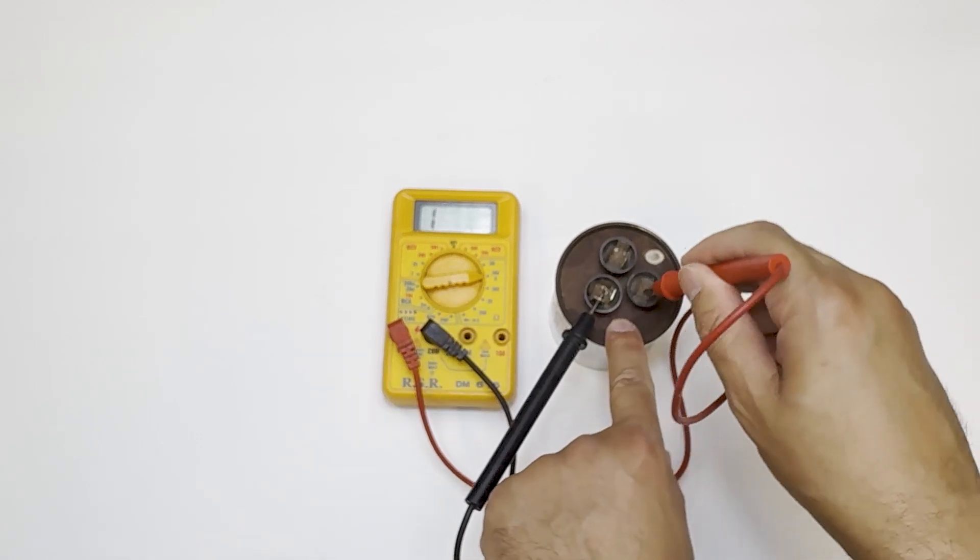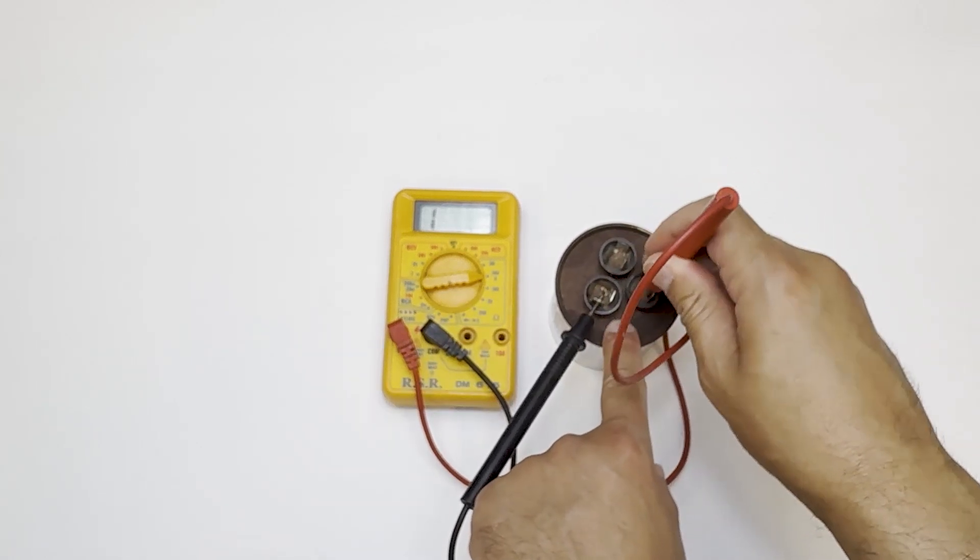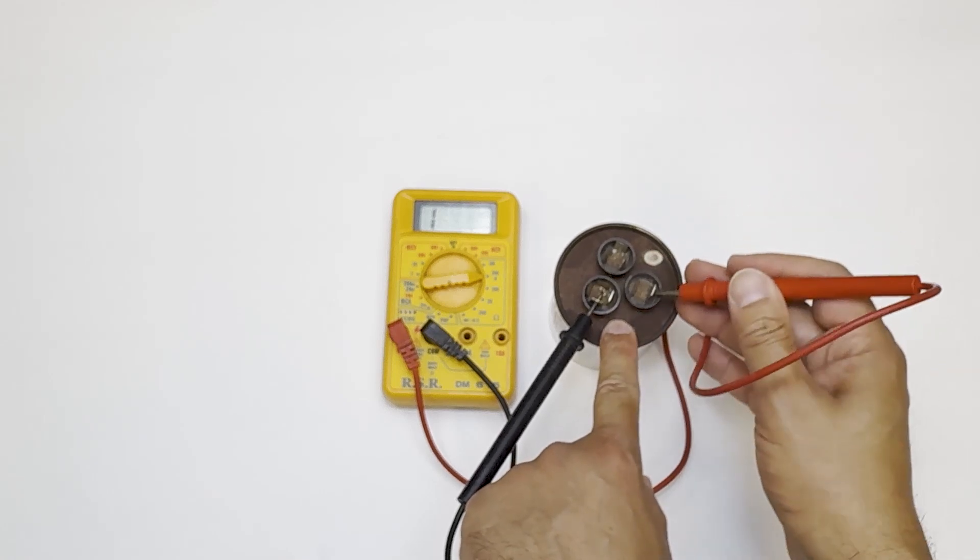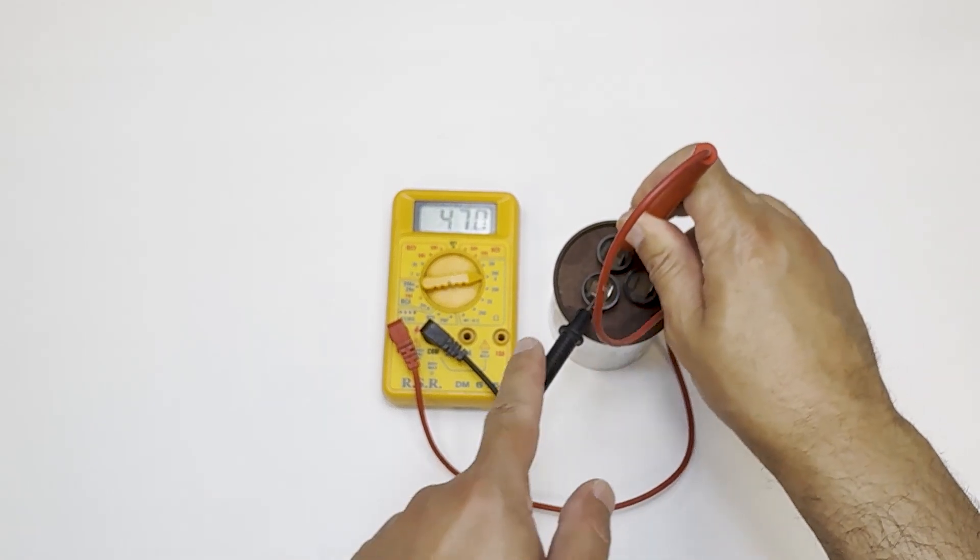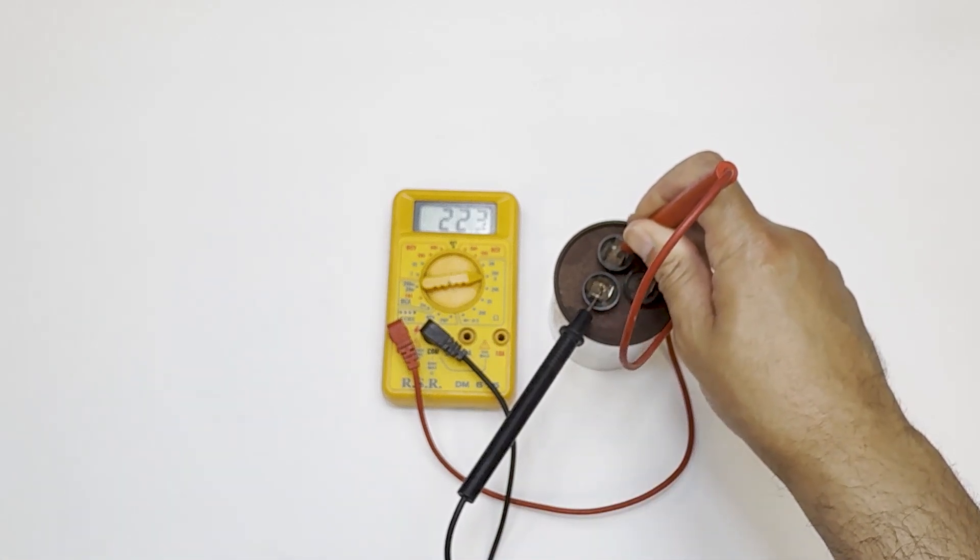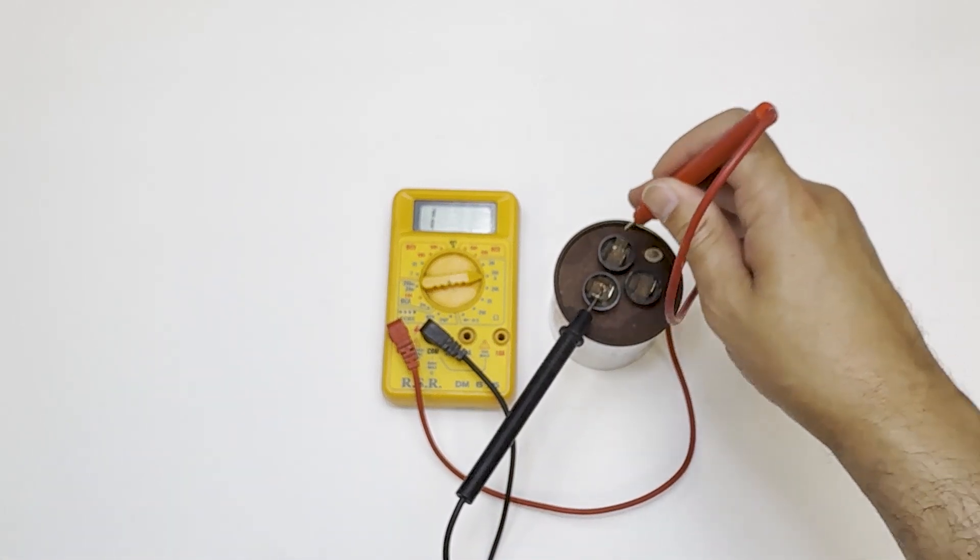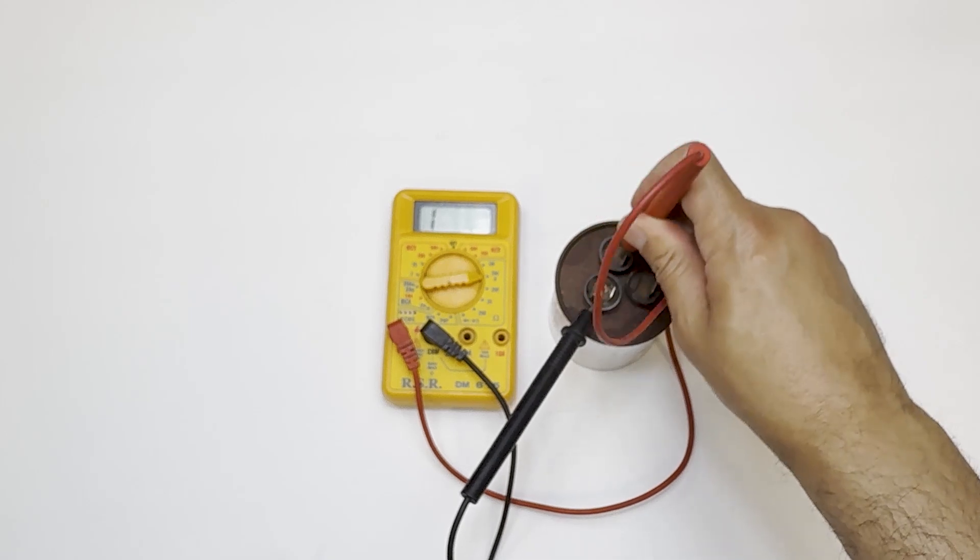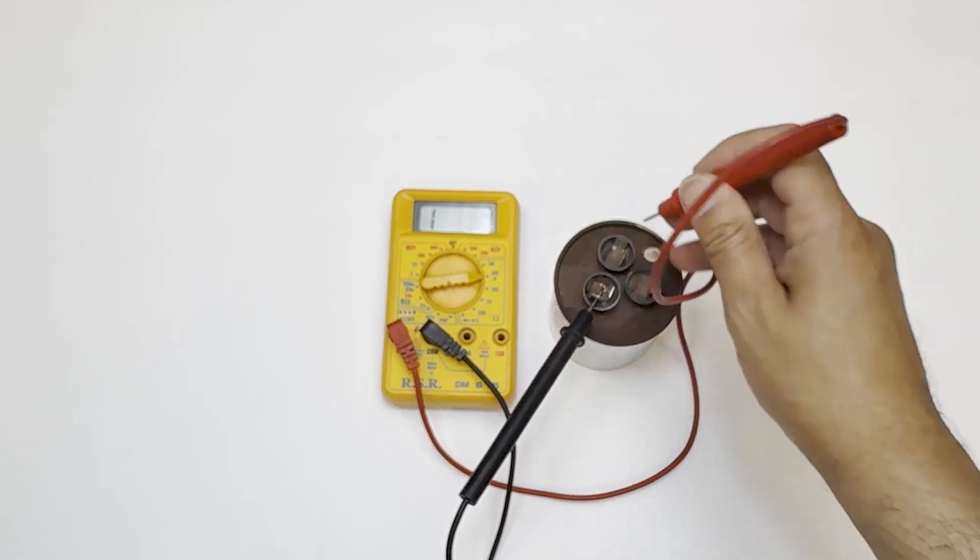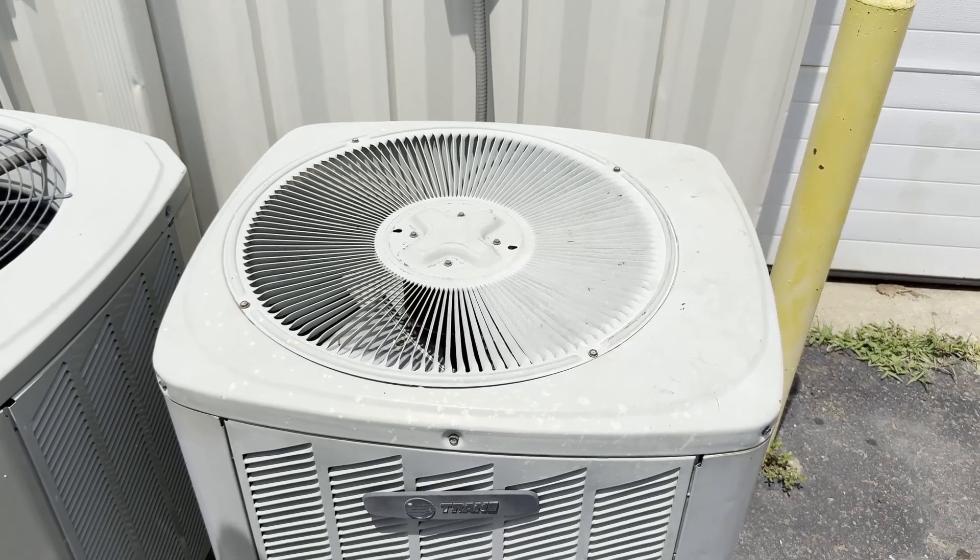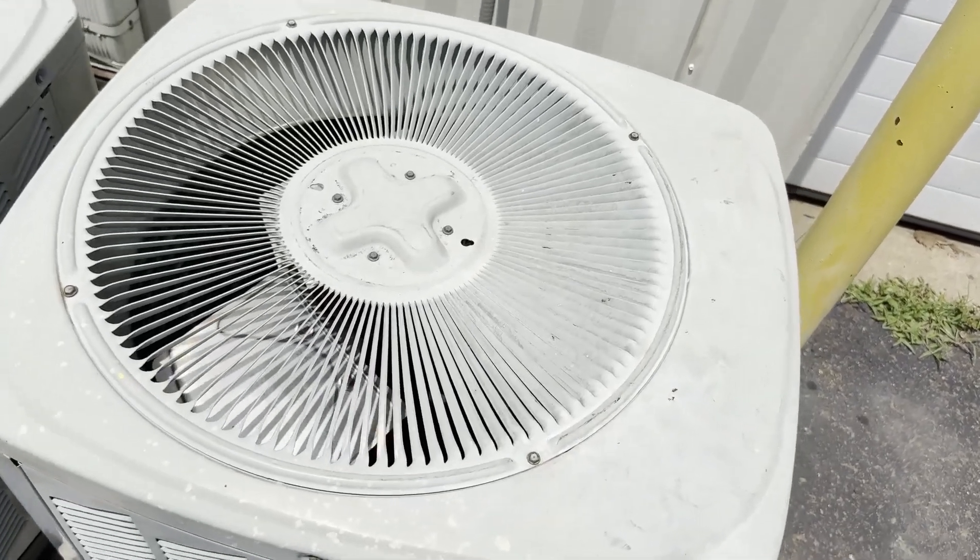Let's test the fan side first. And nothing. It stays at 1. The meter doesn't move at all, so that part of the capacitor is dead. Now let's try the herm side. You'll see the meter jumps and climbs, then eventually drops back. So the compressor side still kind of works, but since one side is shot, the whole capacitor is basically useless. Based on this and the sound we heard earlier, the compressor running and the fan not running, we know that the fan side of the capacitor is dead.